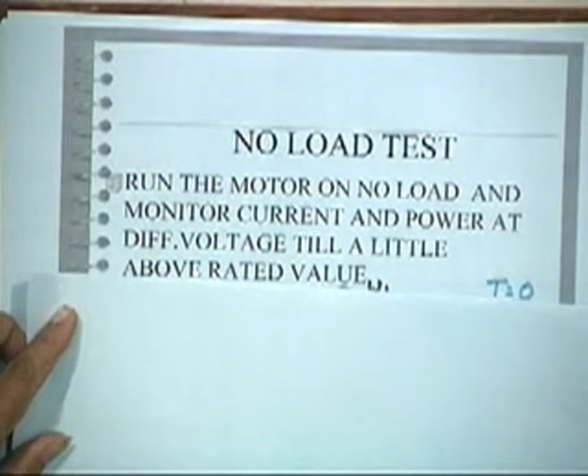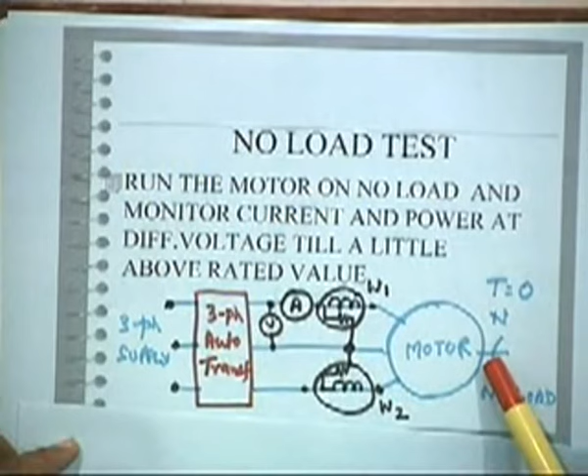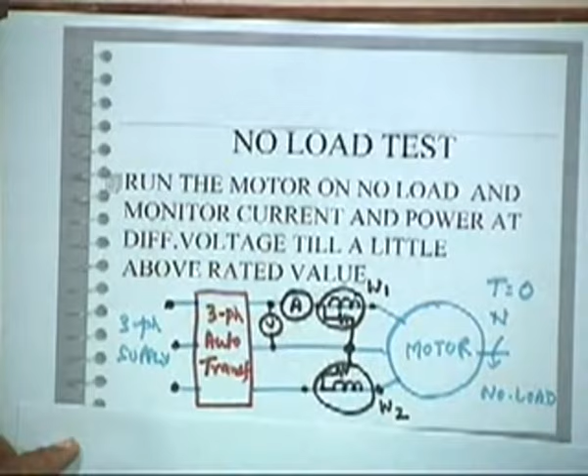So the circuit diagram that you will use will be typically as follows. You have the motor, and you have the instrumentation - the voltmeter, ammeter, wattmeters - to measure the voltage, current and power, and you connect to the supply through a variac or auto transformer, because the auto transformer facilitates you to vary the voltage across the motor. On the shaft side, don't connect anything - it should be no load. That's why it's called no load - there is a speed, no load speed, but there is no torque. So this is the circuit diagram that is used for a no load test.